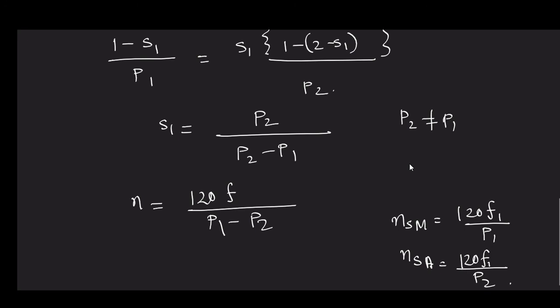Therefore the machine will start to accelerate, and as soon as the machine starts accelerating, your slip value will reduce. And we know that in our stable operating zone, if we reduce the value of slip, there is less torque. So this will continue until the torque demand and your machine speed are matched. And once they get matched, by injecting this additional EMF at your rotor circuit, you can operate your machine at the highest speed.